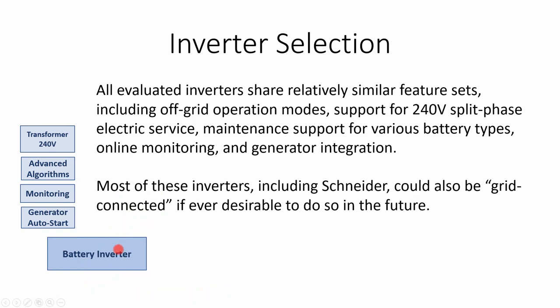Some battery inverters are built for either the European market on a 230 volt or 50 hertz signal, or like the Australian market. Some battery inverters are coming from small cabins that might only be on 120 volts, or like RVs that are on 24 volt batteries with 120 volt outputs. And so I'm thinking about SMA, they make a 120 volt battery inverter. And so sometimes you have to add a 240 volt transformer on top of that.